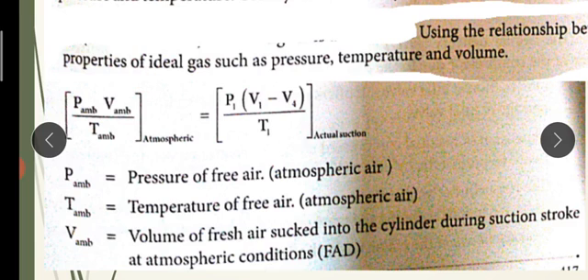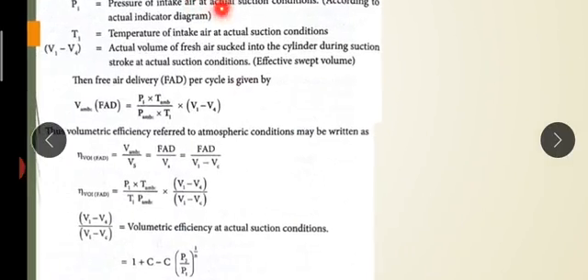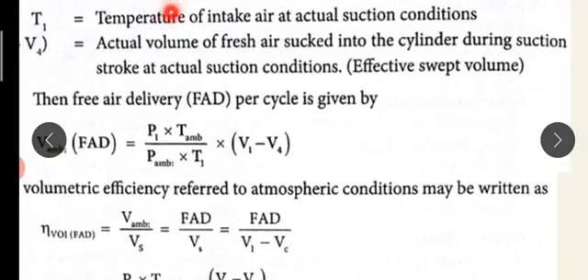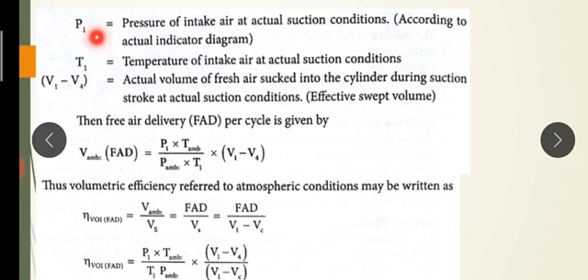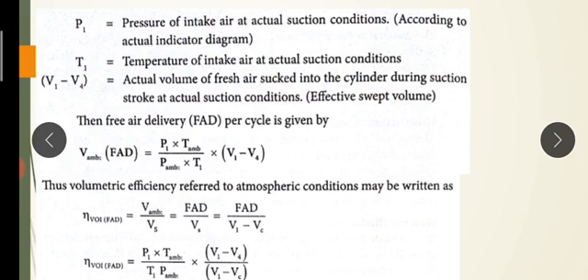According to the properties of the ideal gas equation, we are going to apply the ambient conditions. P1 is the pressure of intake air at actual suction condition, T1 is the temperature of intake air at actual suction condition, and V1 minus V4 is the actual volume of fresh air sucked into the cylinder during the suction stroke — this is the effective suction volume. Free air delivery per cycle is then derived.